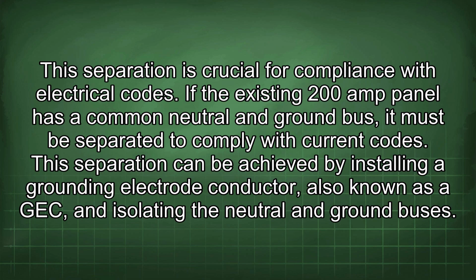If the existing 200 amp panel has a common neutral and ground bus, it must be separated to comply with current codes. This separation can be achieved by installing a grounding electrode conductor, also known as a GEC, and isolating the neutral and ground buses.